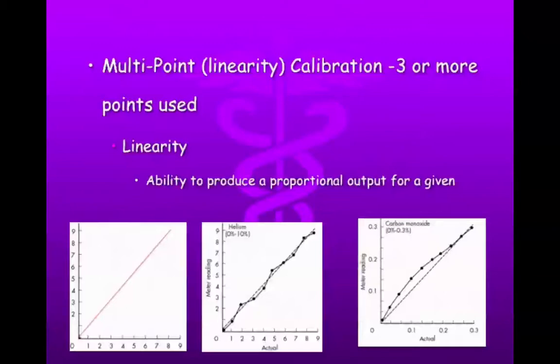When we look at calibration, we look at things like what we call linearity. Are we able to produce the expected outcomes in a linear fashion? So these different graphs here, if you look at the graph over to the left, is showing what a true linearity line is. It goes straight across. A slightly variable linearity is still linear, because here's a helium analyzer. It goes a little bit high and a little bit low from that linear line, but as long as it fits within the acceptable ranges, that is still considered linear.